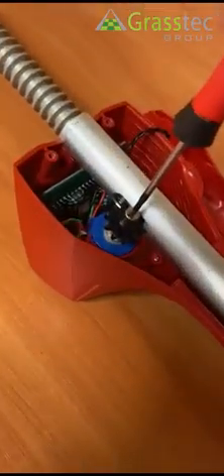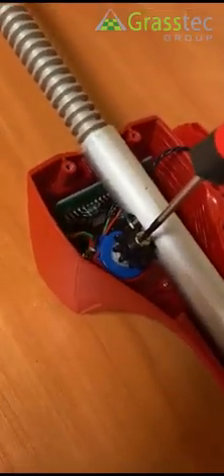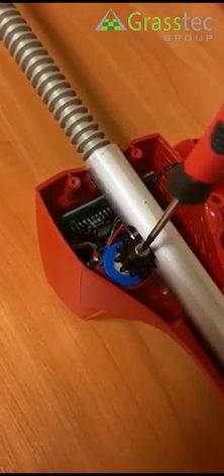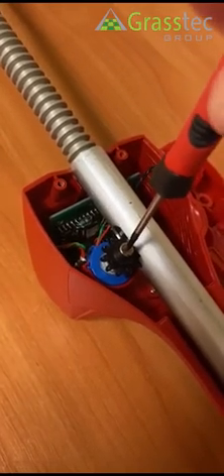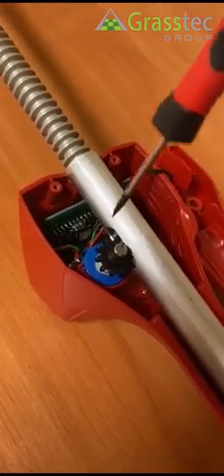The most important thing when fitting the counter is this silver screw here. It's important that this is back anti-clockwise as far as it can go. Where it is here currently, it won't do readings properly. We just have to make sure that it's always turned back gently left anti-clockwise to the left where it doesn't turn anymore—it'll do all the readings.